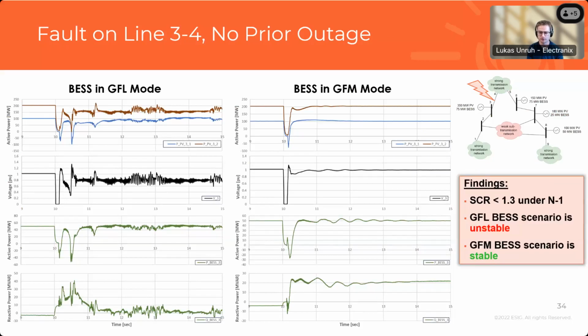So yeah, I'll walk through a few of the specific faults that we looked at. This one here is a fault on that left corridor that removes one of the connections to the strong system for that 350 megawatt PV and 75 megawatt BESS plant there. This is just an N-1, and when that 75 megawatt BESS was in grid following mode, we had the instability that's visible on the left here. So the plants can't recover.